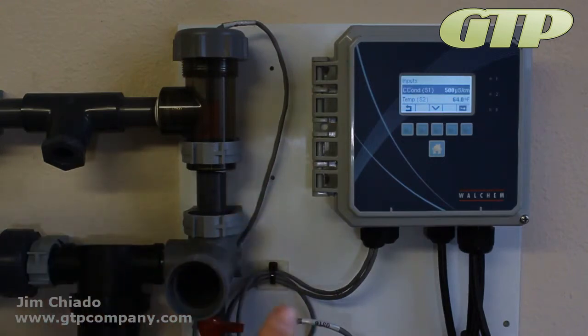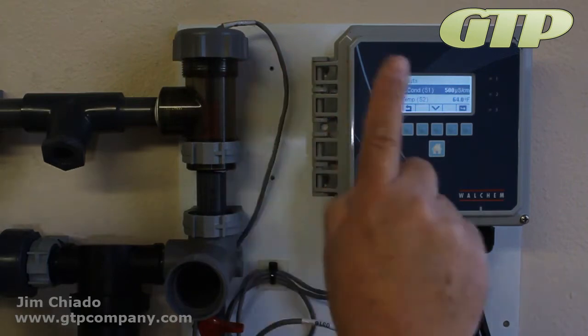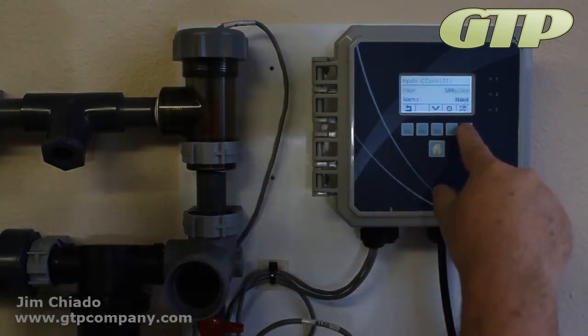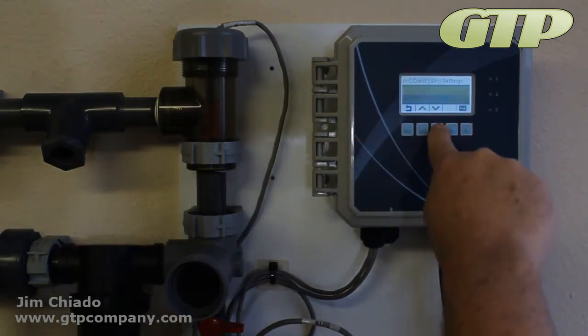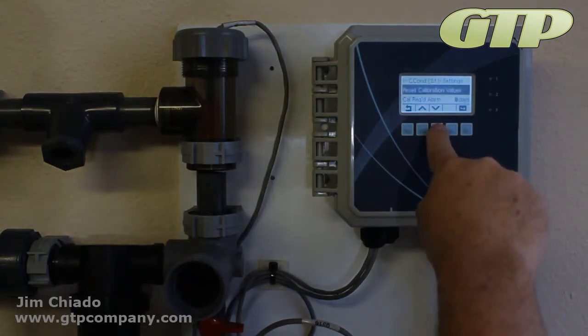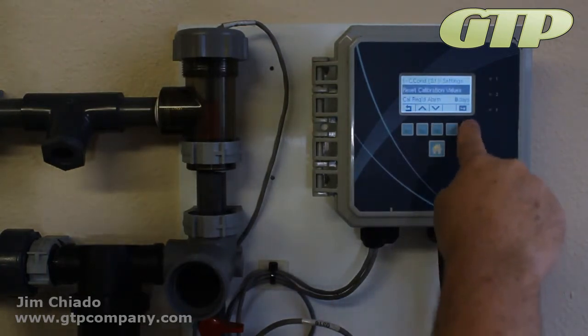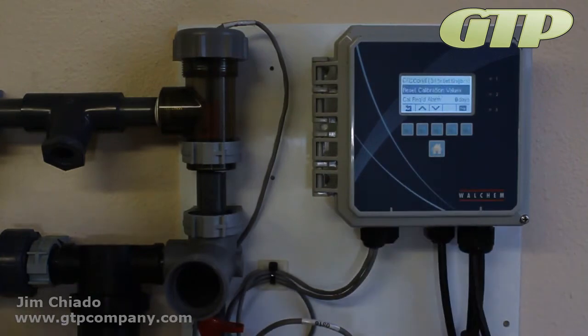The only other thing you want to maintain is that when you replace a sensor, you want to clear the calibration history. If I go here, I go to maintenance. There's one in here, reset calibration values. You do want to reset the calibration values when you replace a sensor. It gets rid of all the old habits. Okay, very good. Home, back and we're done.